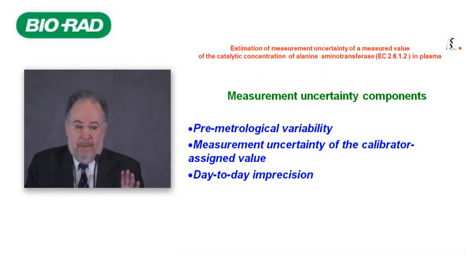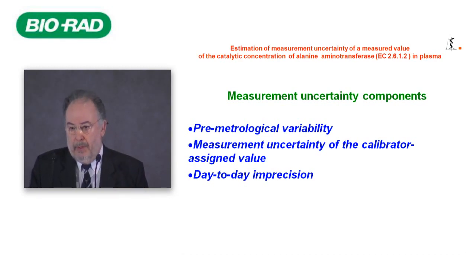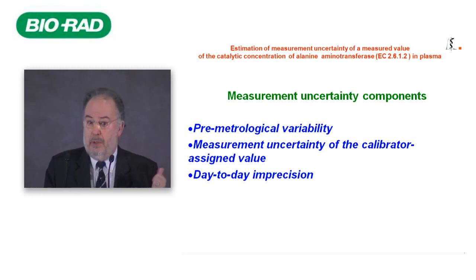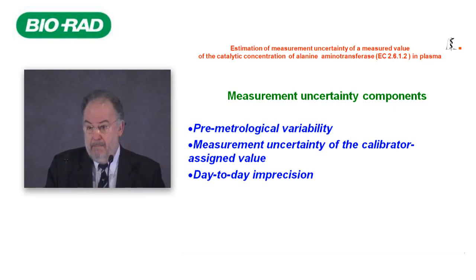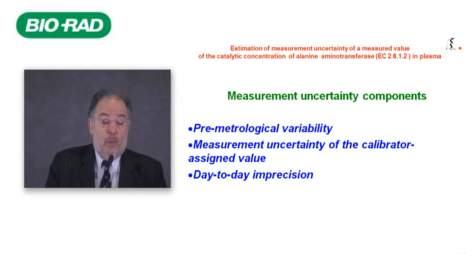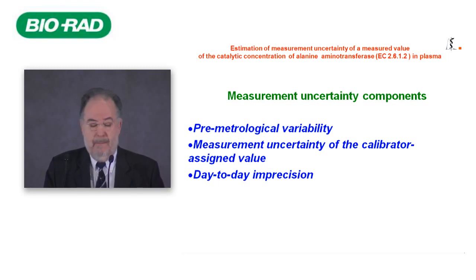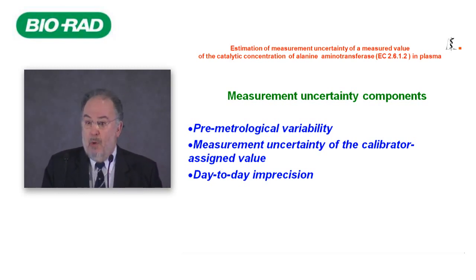After describing the measuring system, we must consider the different sources of uncertainty that can affect the measured value. Among others, the most important are: pre-analytical or pre-examination variability; the measurement uncertainty of the calibrator's assigned value; and finally, generally the most important source of uncertainty — the day-to-day imprecision.